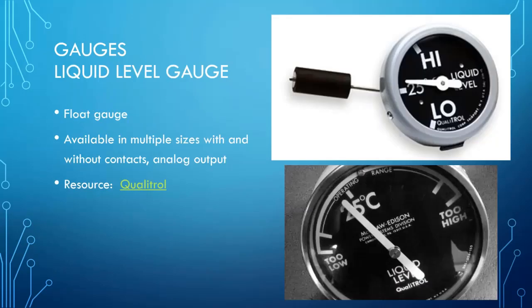So here's some examples of a liquid level gauge. And the reason for this gauge should be obvious, but for those of you new to transformers, we want to make sure that the level of liquid in the transformer is always above the core and coil assembly to make sure it's getting sufficient cooling. If oil somehow leaks out of the transformer, very shortly the transformer will build up too much heat and will fail due to continued over temperature. So it's a simple gauge.